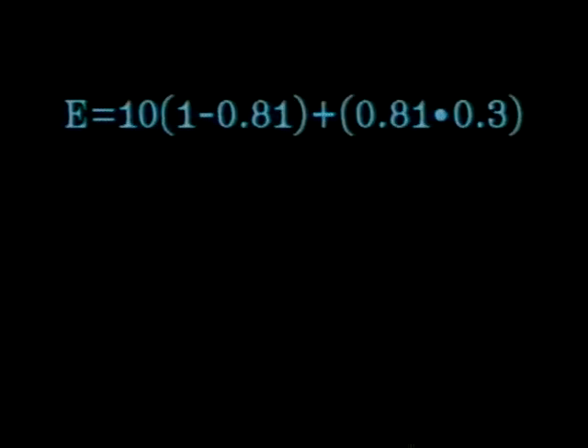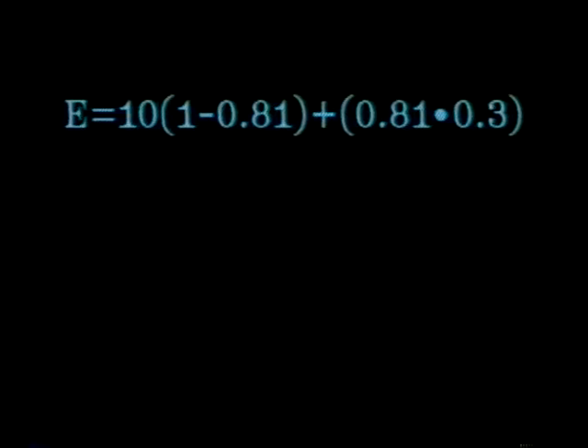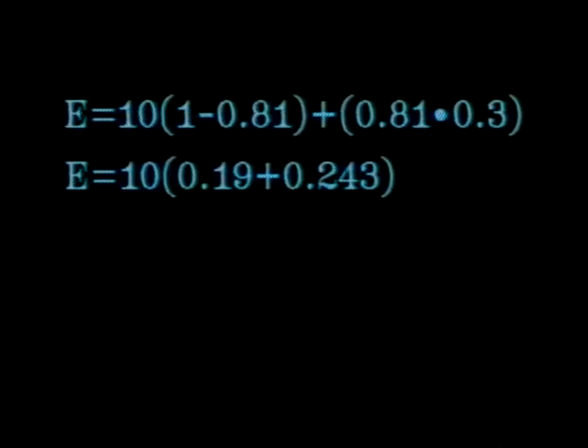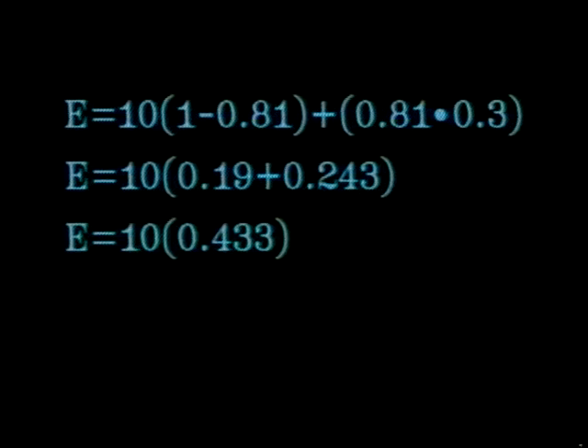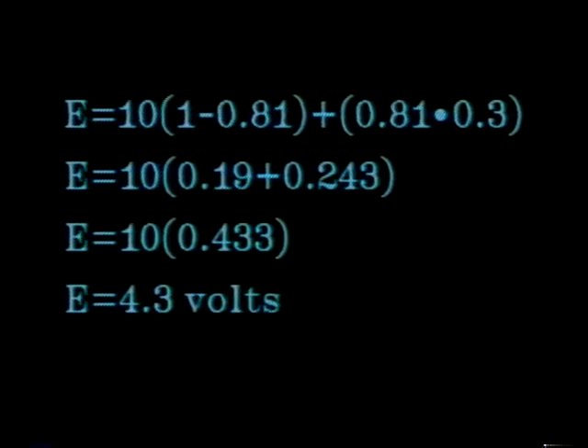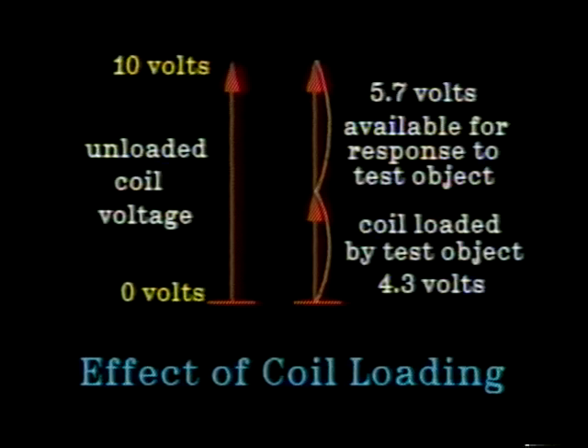When the non-magnetic test object is inserted into the test coil, the coil's voltage will decrease. For example, E equals 10 times the sum of (1 minus 0.81) plus (0.81 times 0.3), which equals 10 times (0.19 plus 0.243), which in turn equals 10 times 0.433, or 4.3 volts. This allows 10 minus 4.3, or 5.7 volts, available to respond to test object changes caused by discontinuities or decreases in the effective conductivity of the test object.